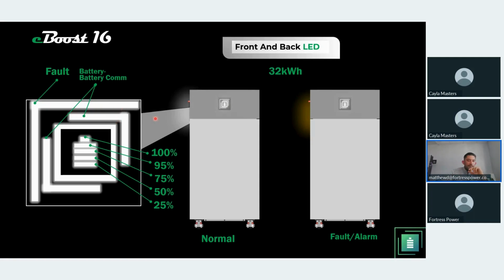And then if there is a fault, you will see this light up and everything else go black, signaling to the customer and to the installer that there is a fault or an alarm occurring, right? And you will get a double confirmation. You will get it from the front LED, and then you would also get it from the back LED. The battery provides a back LED where, if it's normal, it lights up white. If there's a fault or an alarm, it will light up yellow, okay?